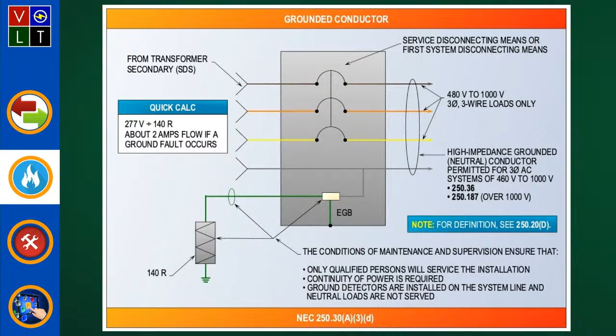One of the things, when you go look at 70E, we discuss this, because this is a type of system you'd use to help clear that fault quickly, which limits the arc exposure to you. That's ultimately what that NGR is doing, bringing the incident energy out of the gear outside, so that incident energy happens next to a building versus inside the control room.